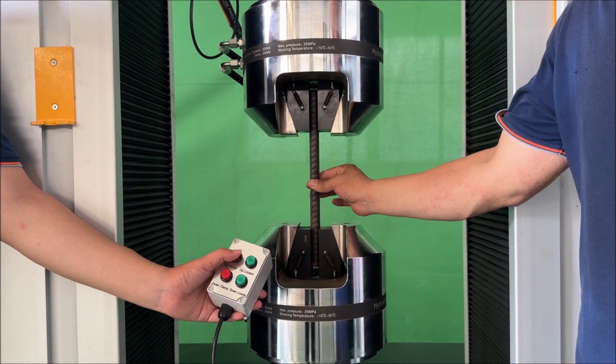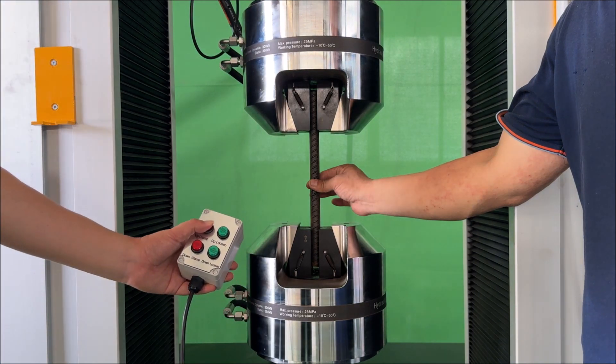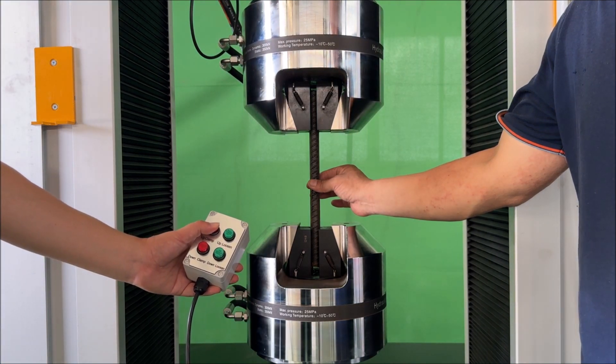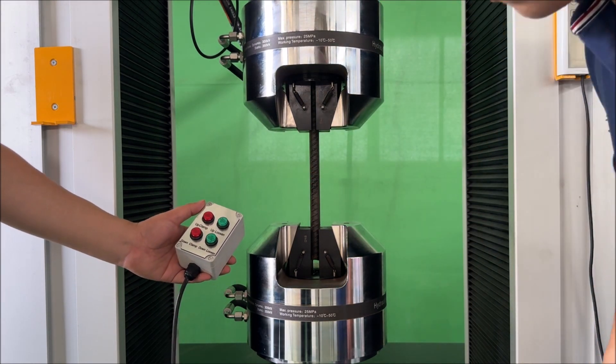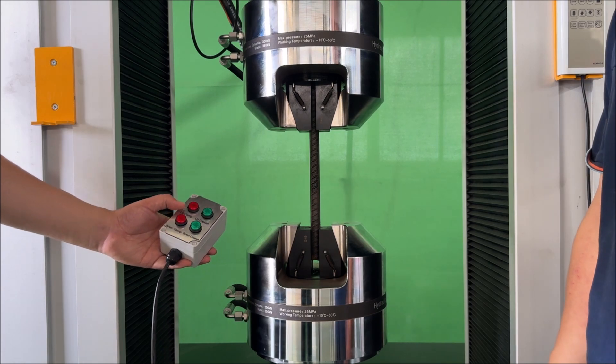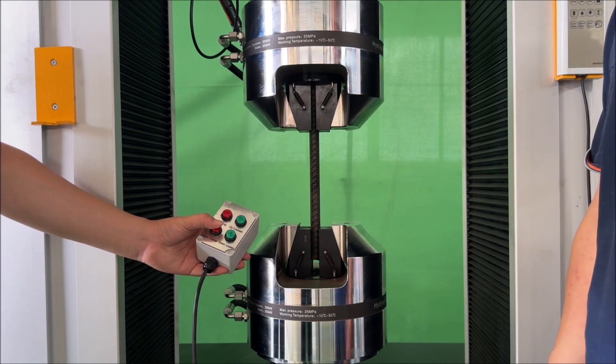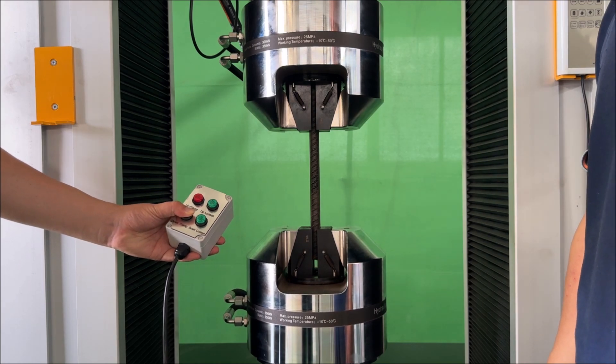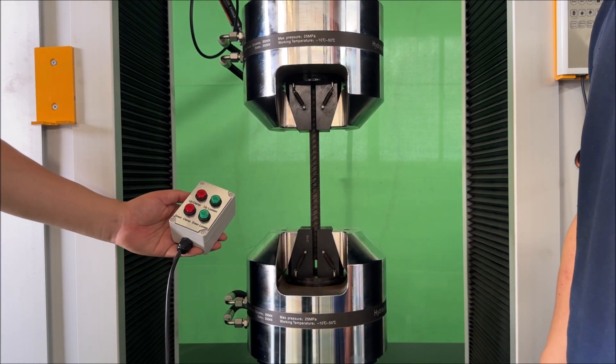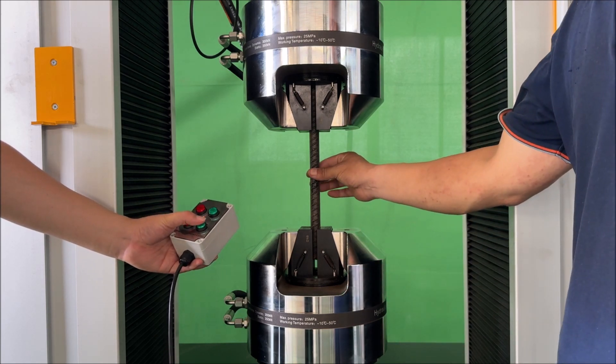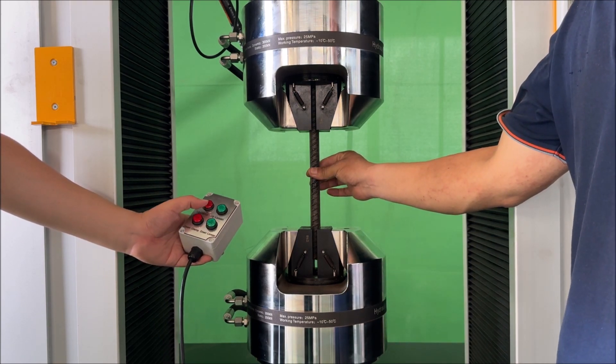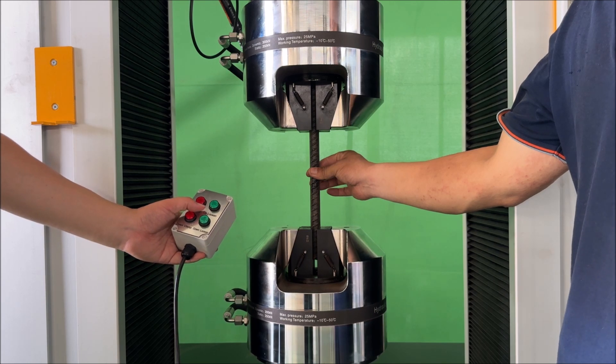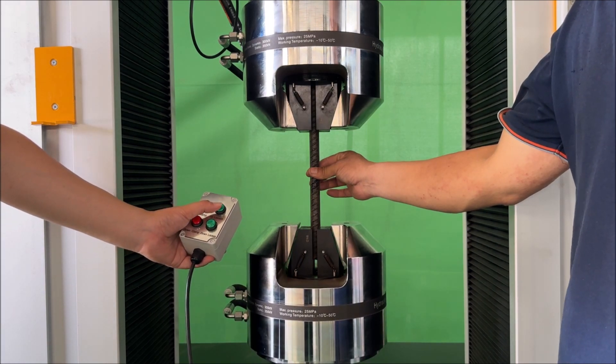First, press and hold the upper clamp button. When the pressure exceeds 2 megapascals, release the button. Then press the down clamp button. Once the clamping pressure reaches 15 megapascals, you can press down loosen, and finally press up loosen.